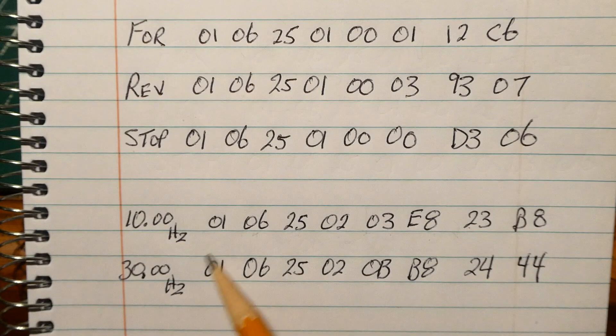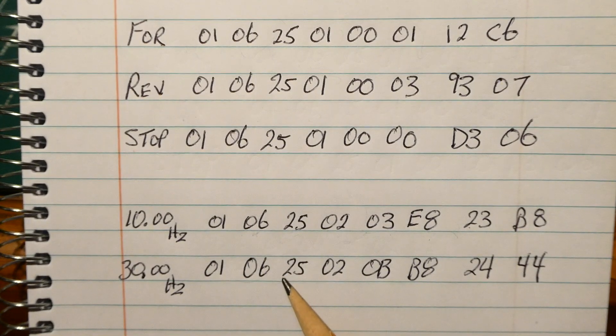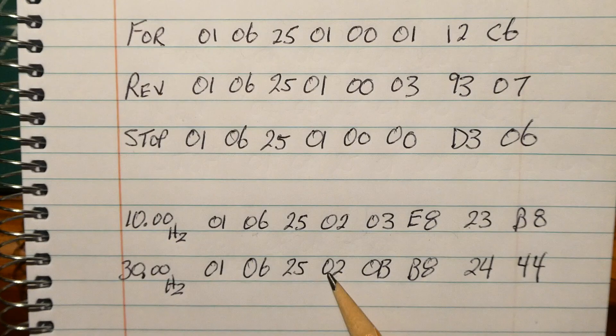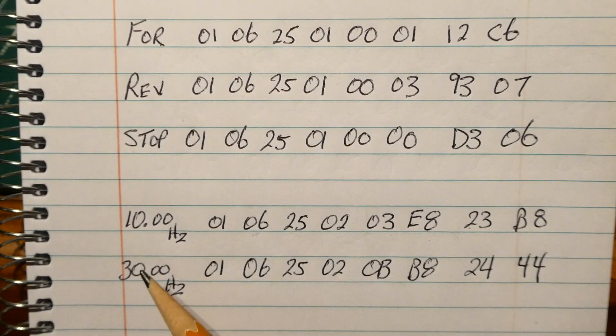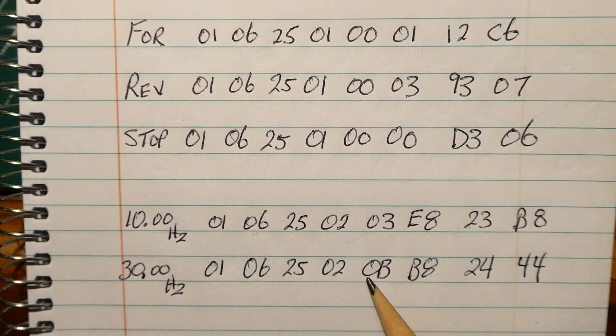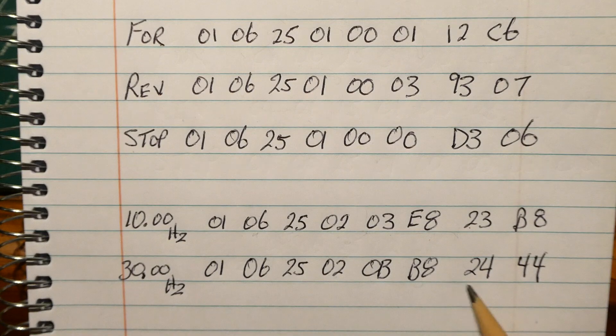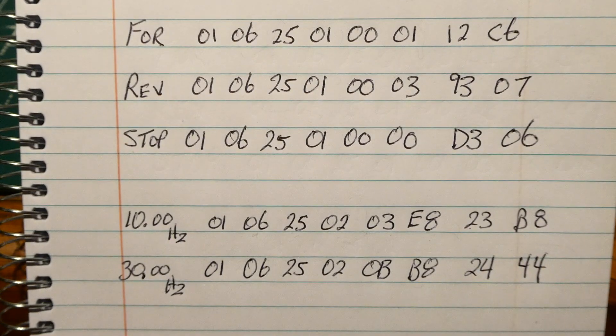And also for 30 hertz, address is 1, 06 means a write, we're writing to register 2502. Now if we take 3000, change that to hex, that will be 0B, B8, and then the last two bytes is our CRC checksum.